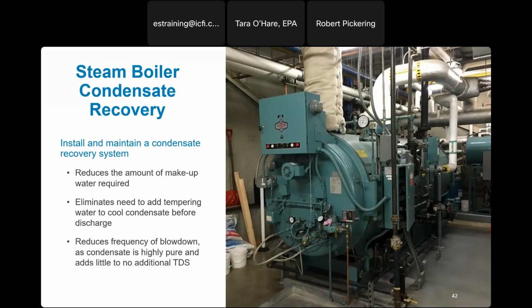The most important feature of an efficient steam boiler system is capturing that steam condensate and returning it to the boiler. The water savings are threefold. First, you're returning this high quality hot water to the system, which both reduces the water use and the energy demand on the boiler system. It also eliminates the need for tempering water to cool the condensate before it's discharged. And lastly, it reduces the frequency of blowdown, since the condensate is high quality water with low mineral concentration.